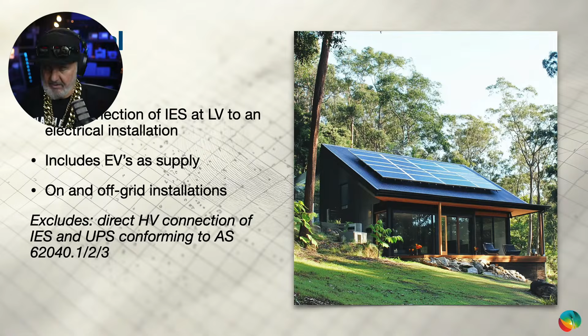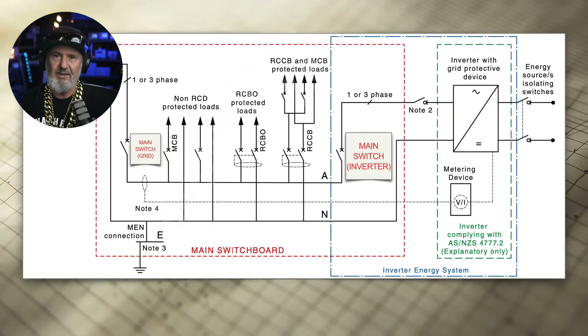We just call it an IES with an energy source. If you look on the right-hand side of this diagram, energy source, the reason for this as opposed to saying PV is that an inverter can be supplied with energy from multiple means, such as wind, hydro, solar - they're all energy sources, or even a battery as an energy source. The inverter, if it's connected to the utility grid, needs to comply with the safety standard for inverters, 4777 Part 2, 2020. That standard has been in use in New Zealand for some time because it's actually a product standard, not an installation standard. And of course, you can't even buy inverters compliant to older versions of this product standard anymore, so they will all have the latest.